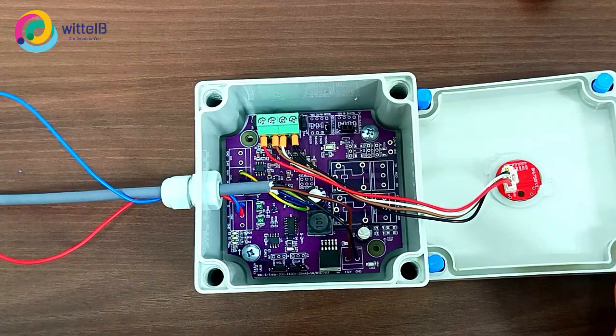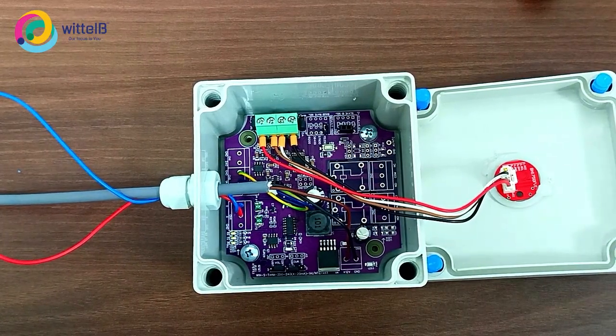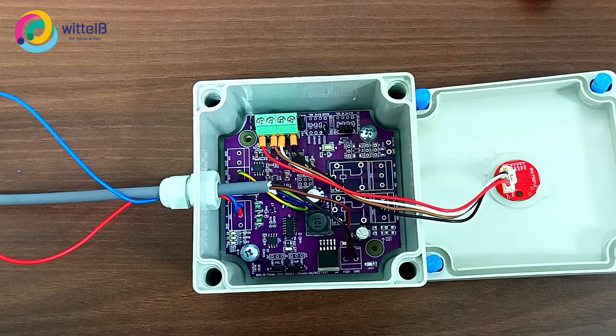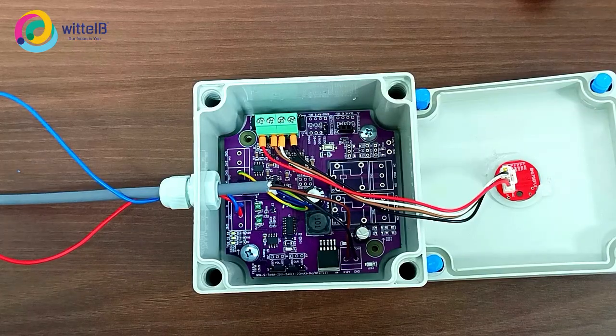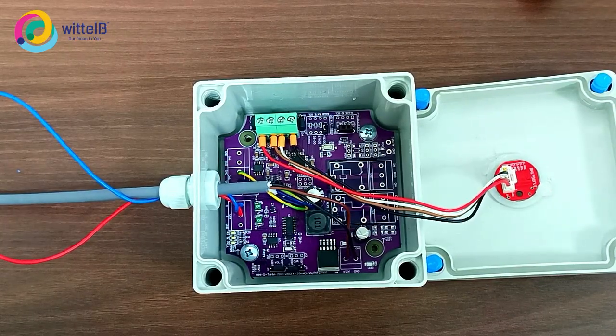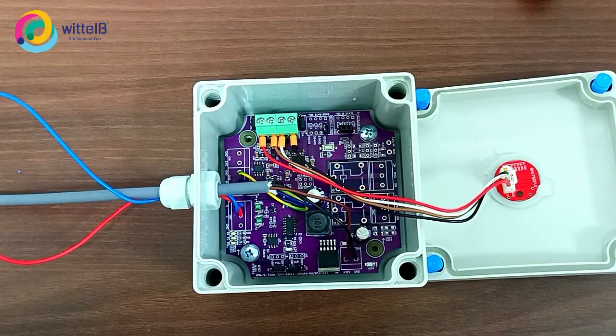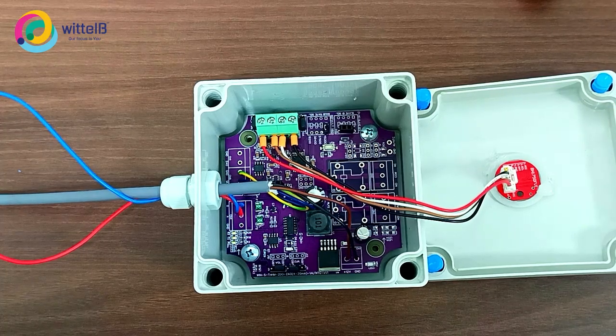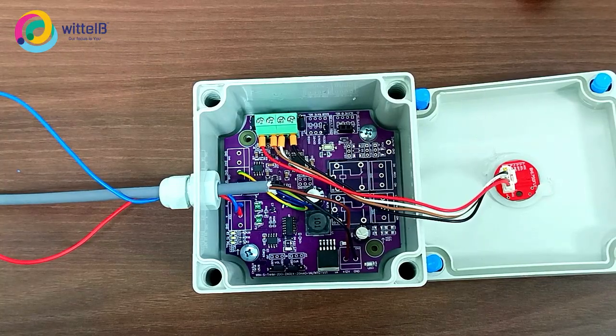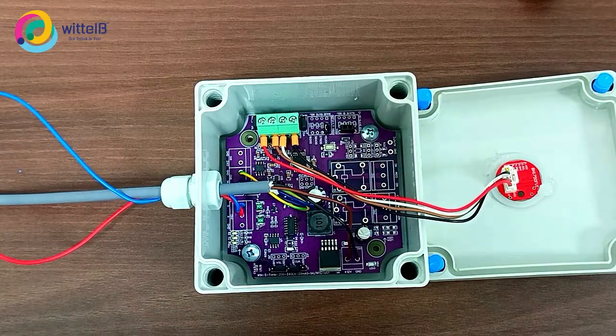This function is used in industrial lighting and illumination control systems, where the LED and the light source operate together with the Lux sensor in a closed loop configuration. The system continuously compares the Lux value with the user defined calibration, where the user sets the start and end ranges, and the driver continuously compares the measured Lux. Then it automatically adjusts the analog output to achieve the required light intensity.